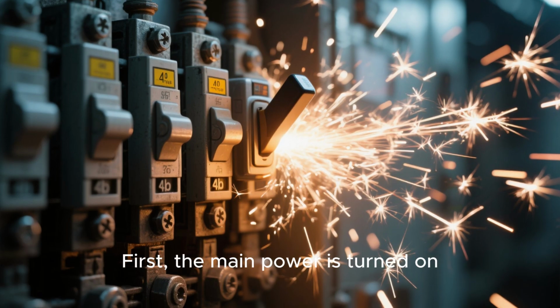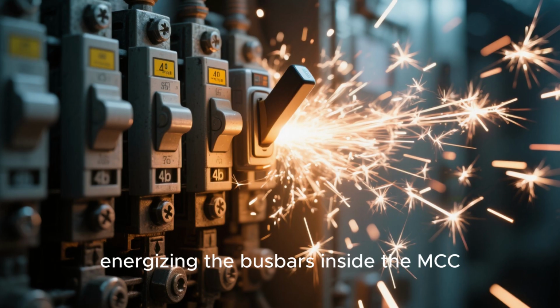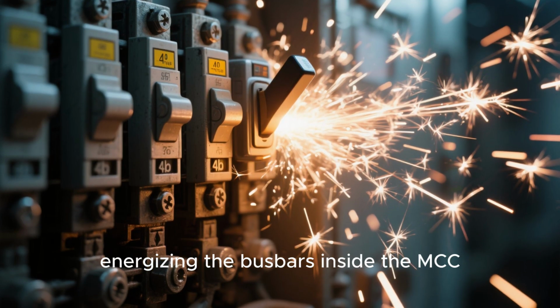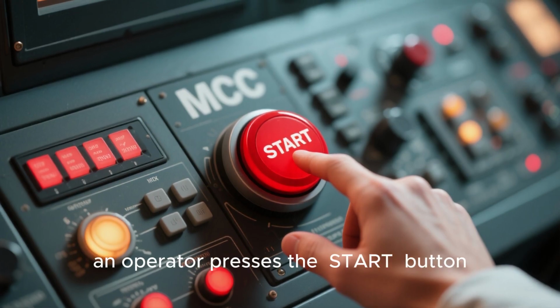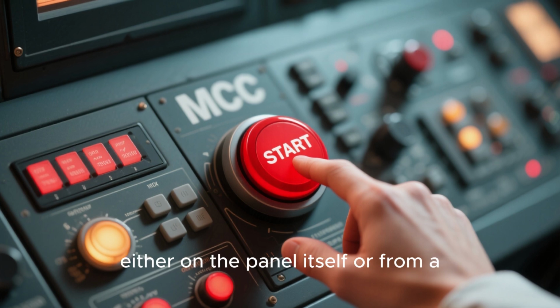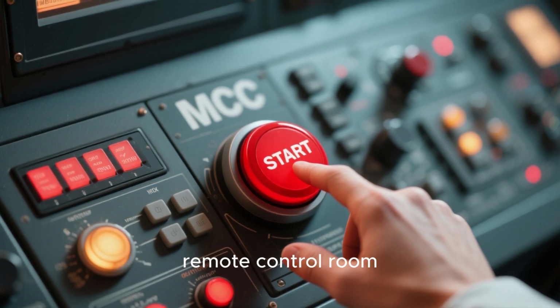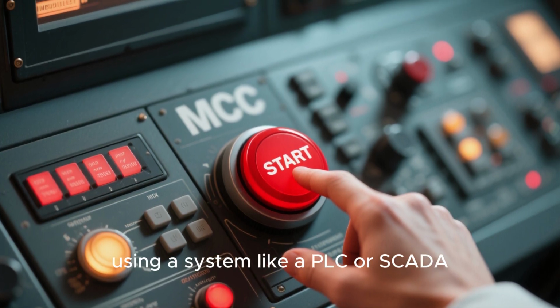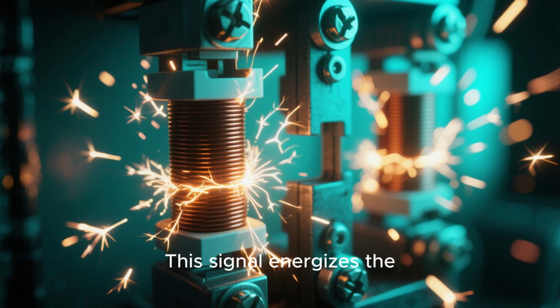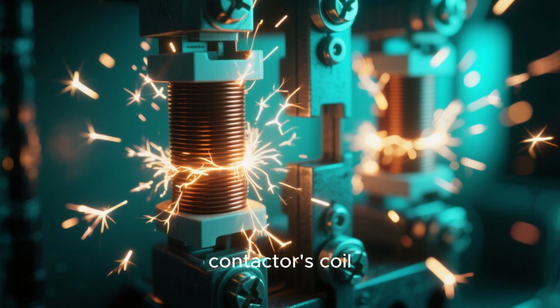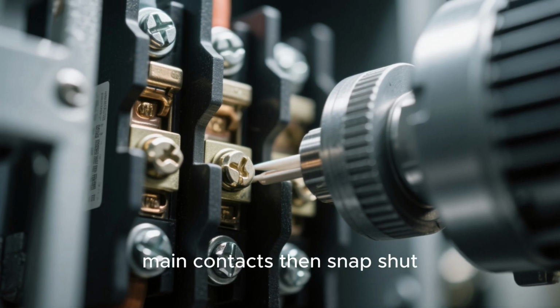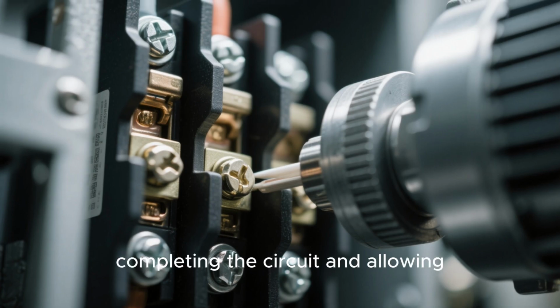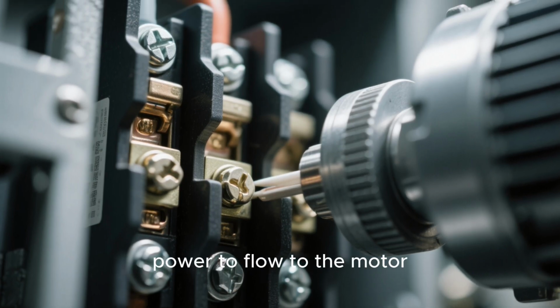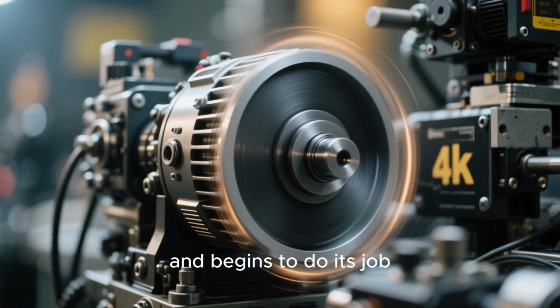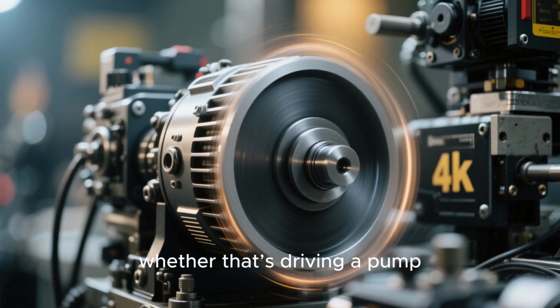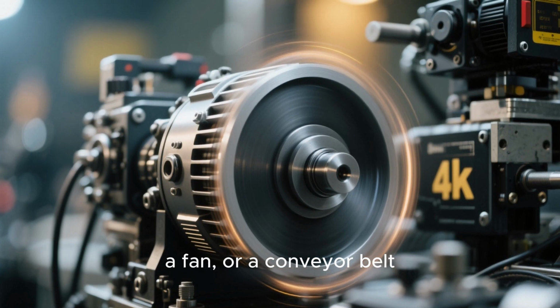First, the main power is turned on, energizing the bus bars inside the MCC. Then, an operator presses the start button, either on the panel itself or from a remote control room using a system like a PLC or SCADA. This signal energizes the contactor's coil. The contactor's main contacts then snap shut, completing the circuit and allowing power to flow to the motor.